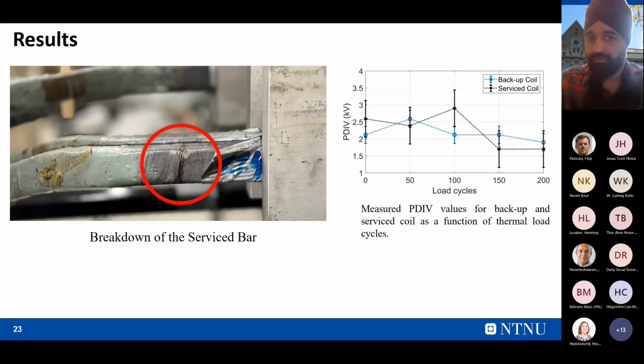So these are the PDIV values. PDIV values are basically the partial discharge inception voltage, the point at which partial discharge just begins. These are the inception voltages of the partial discharge. These machines are rated for 1.9 kV line-to-ground voltage, and for the service coil we found that these values are much lower as we increase the load cycles, compared to the backup coil.